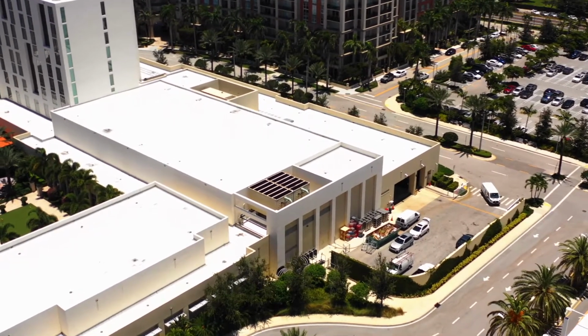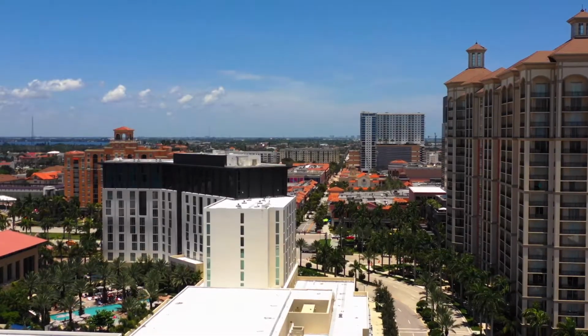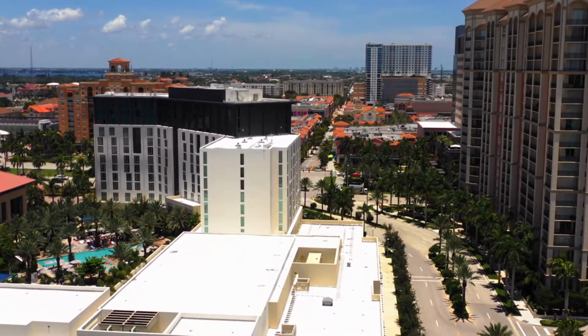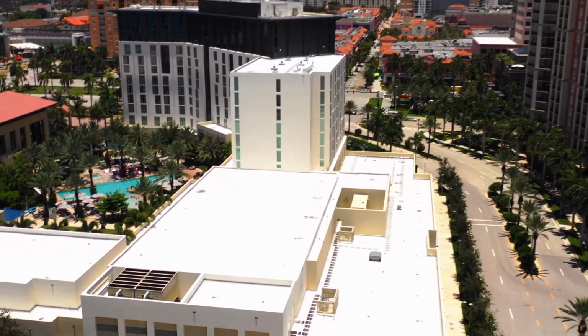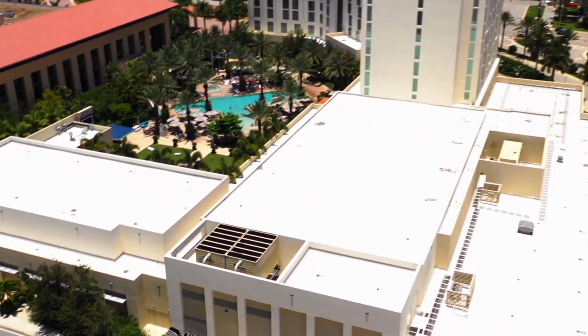So from the perspective of success, it had all the features: low drift, fiberglass so it would never corrode or rust away, and high efficiency from the multiple fan application. The VFD on that fan application gave us a wide range of performance capability. It just offered every feature I would want in a cooling tower.